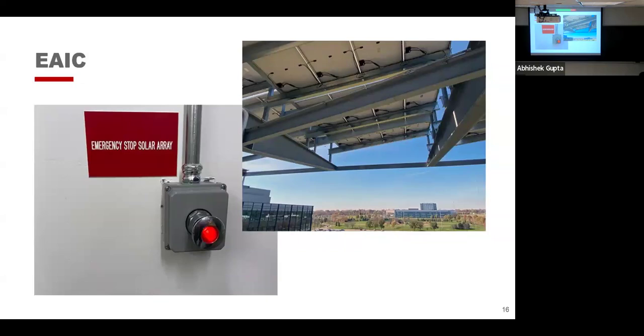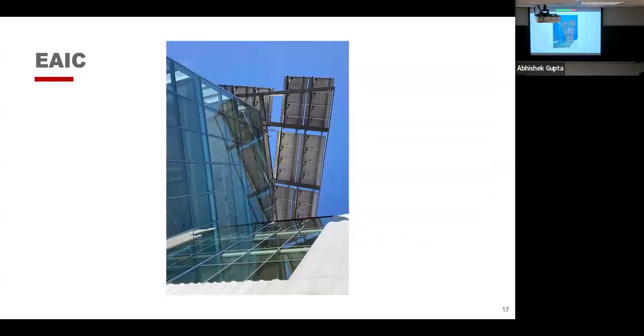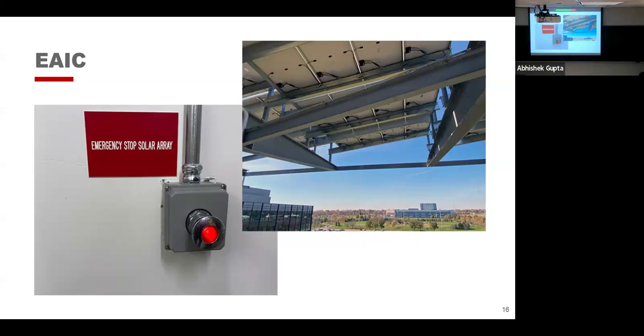That's very dangerous. You'll notice these little black boxes underneath the solar panels. Those are all wireless, and that's how we communicate the rapid shutdown system to turn it off. It's reversed, so it has to have the signal to remain on. If it loses the signal, it goes off and shuts power to those devices. So these boxes are just giving information, not receiving any? Well, that's right, we do get some information from it, but if there's a communication failure, they'll turn off automatically.